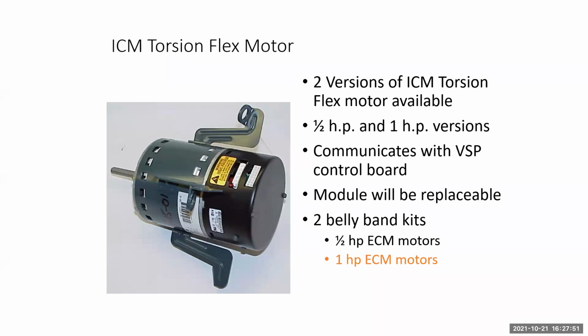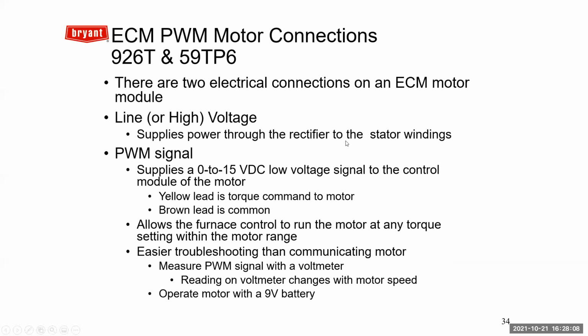Your ICM flex motors, they're half horse and full horse motors. The module is replaceable on these. Here you have your ECM and PWM motors. You're going to have high voltage and low voltage going to these things. Your high voltage is supplied to them 100% of the time that you have high voltage supplied to your furnace. Your low voltage depends on what your signal calls are. Your brown wire is going to be jumped between your two plugs. Brown is common, yellow is your power wire. You're going to have 0 to 15 volts supplied to that. Keep that in mind. Brown really does nothing except for your common.